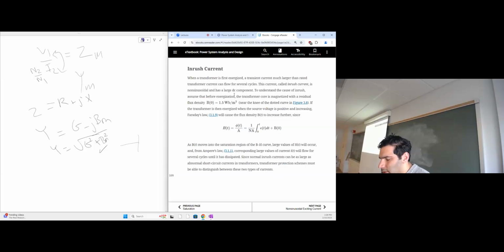Usually those things are typically tested at the validation level. When they make a transformer, they do those tests. They check the starting current, the exciting current, all those things to make sure they are within the limits. Other than that, they cannot sell them, actually. They don't get the approval to sell them.